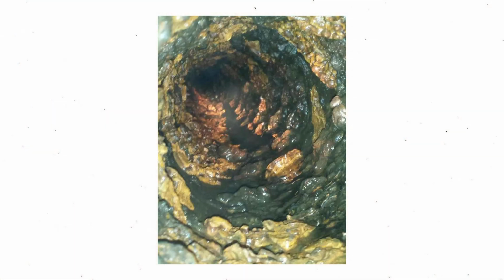This is the point where water pipe size becomes a key factor. The water pipe that supplies the hydrants on Main Street are cast iron and were installed as 6-inch pipes with 100 years of buildup of scale, incrustation, and sedimentation that is inside these pipes. The inside of the pipe is actually only 3 to 4 inches in diameter, flowing 60% less water at a lower pressure.